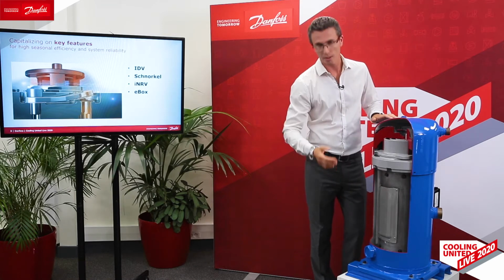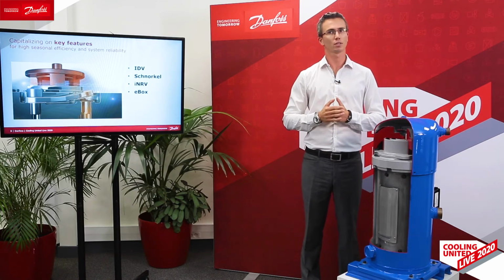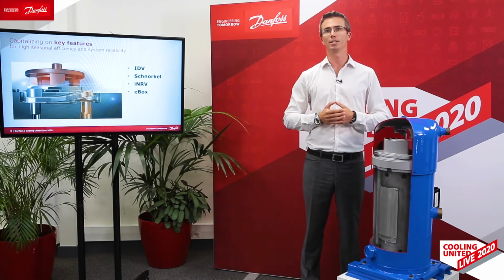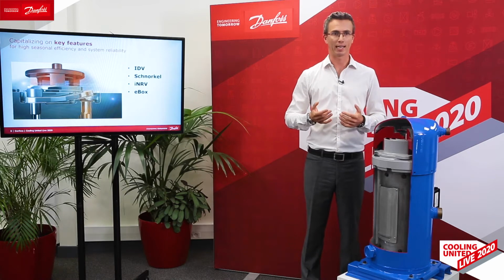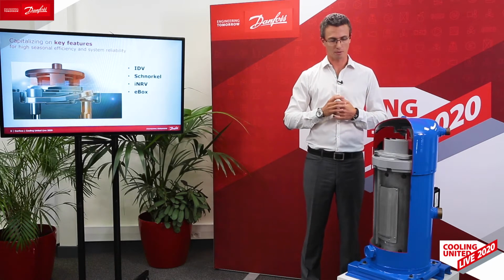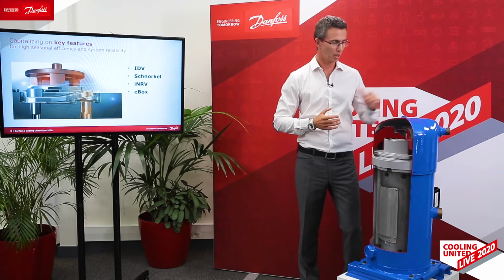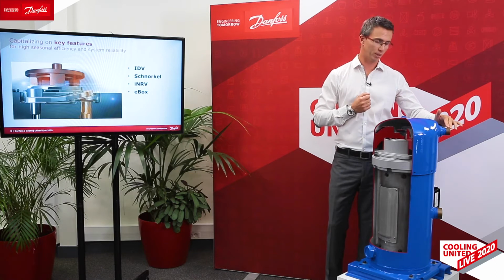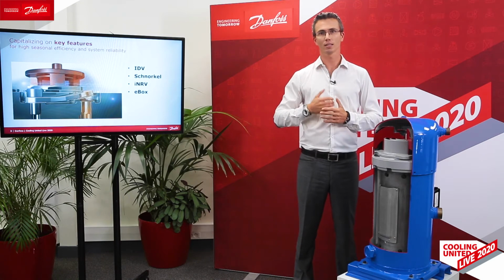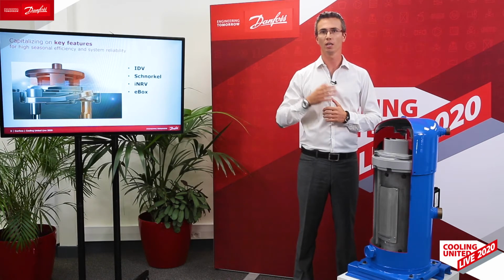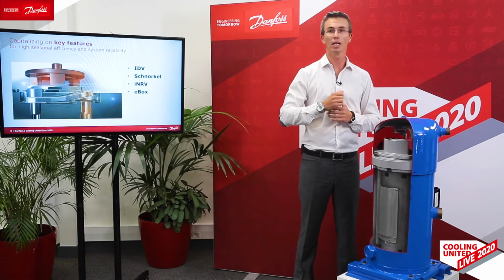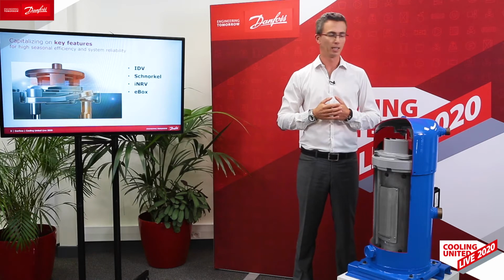The second device I want to show you here is a schnorkel. This device has demonstrated very good flooded start capability because basically it acts as a suction line accumulator. But this is on ranges above 20 ton. Also on the range above 20 ton, here is the internal NRV. You know this device on large scroll above 20 ton, and in the coming months we will have it also on medium scroll starting from 7.5 ton. This device protects against the migration of refrigerant from high pressure side to low pressure side, and then it protects your system and our compressor against dry starts.